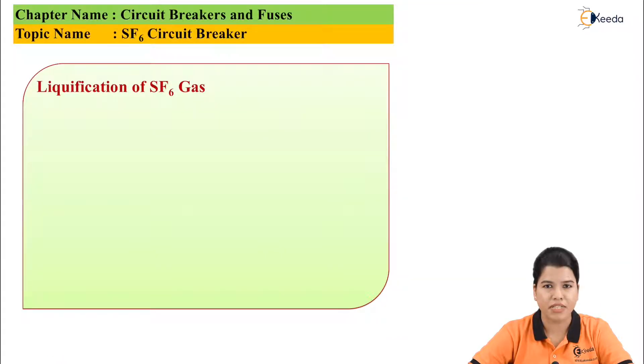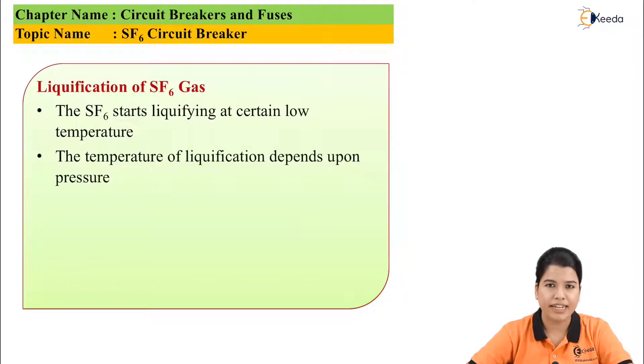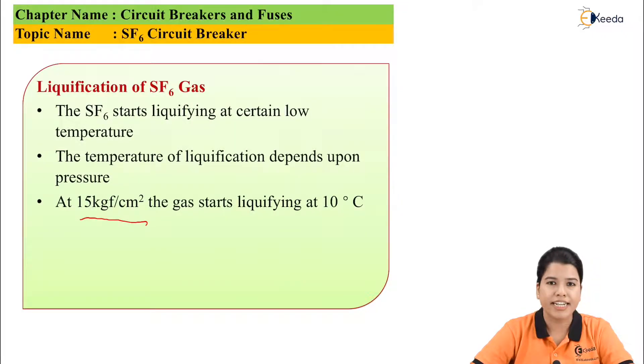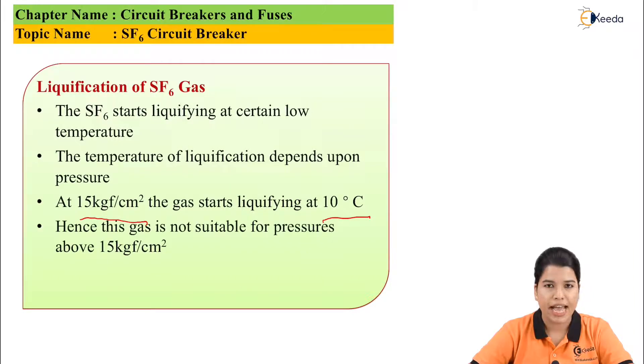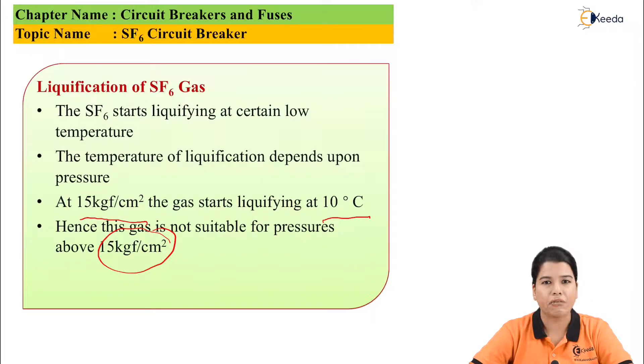The next property is liquefaction of SF6 gas. SF6 gas starts liquefying at a certain temperature, and the temperature of liquefaction depends upon the pressure. At a low temperature, SF6 gas starts liquefying. At a pressure of 15 kgf per centimetre square, the liquefaction process starts at 10 degrees centigrade. As a result, this gas is not suitable at a pressure of 15 kgf per centimetre square and above.